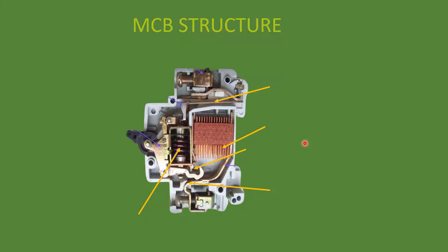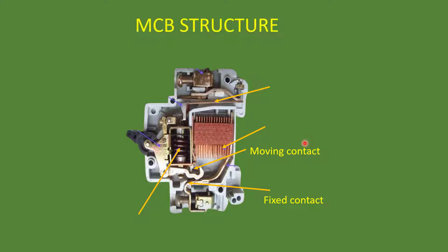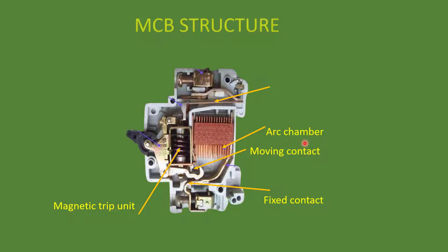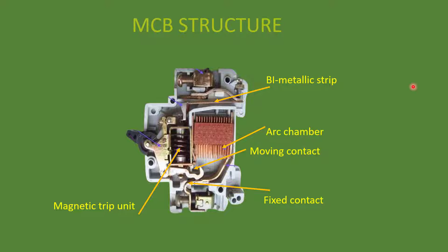Let's look at the components of an MCB and its working principle. Every breaker has two contacts in common: a fixed contact and a moving contact — electricity flows through these contacts. There is also a magnetic trip unit, which is the short circuit protection mechanism, and an arc chamber, used to extinguish the arc. Then there is a bimetallic strip, which is the overload protection mechanism. So in an MCB, the magnetic trip unit provides short circuit protection and the bimetallic strip provides overload protection.